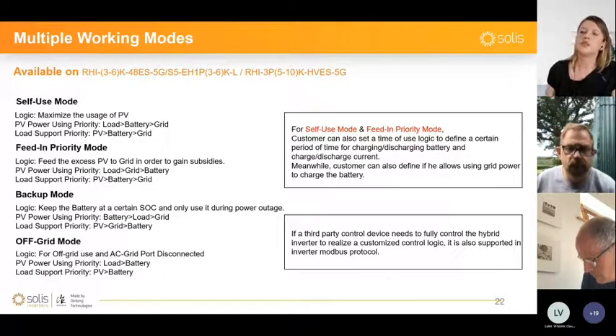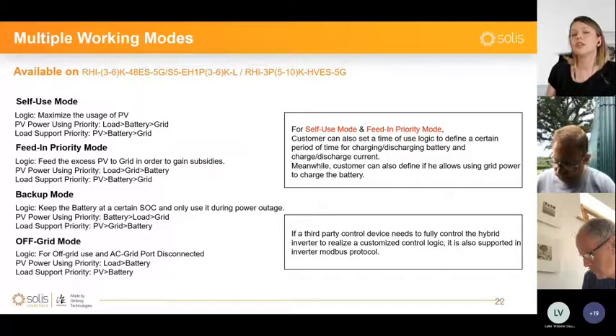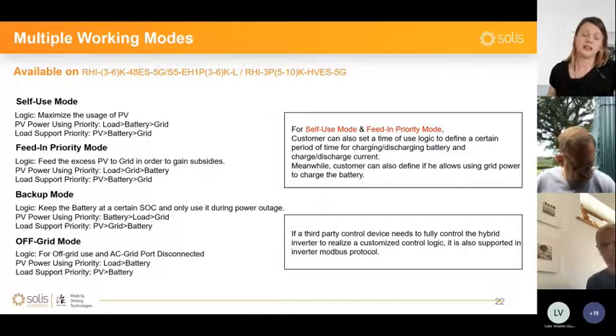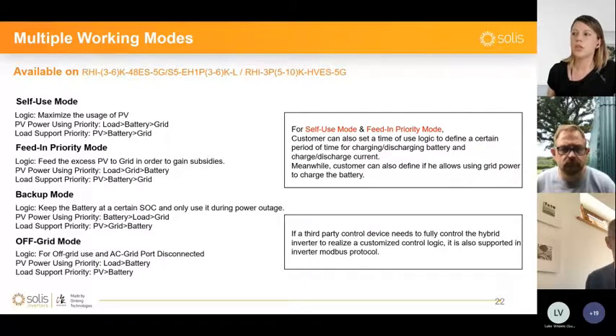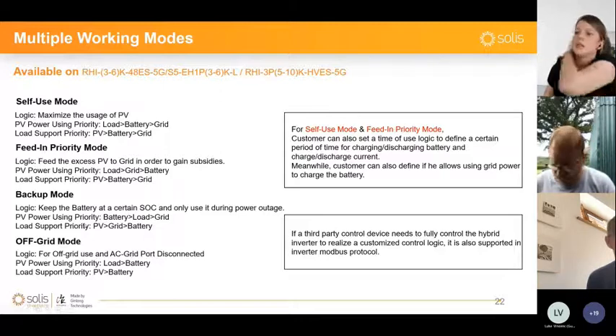But there are other modes, like feed-in priority, that may be used. I don't think this is something that I have ever seen as a need for the UK. Feeding priority: the logic is to feed the excess of PV to the grid in order to gain subsidies. So it's not going to be stored in the battery, but the first option would be to have it injected into the grid in order to gain tariffs.